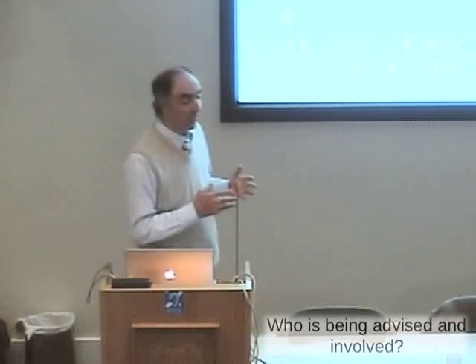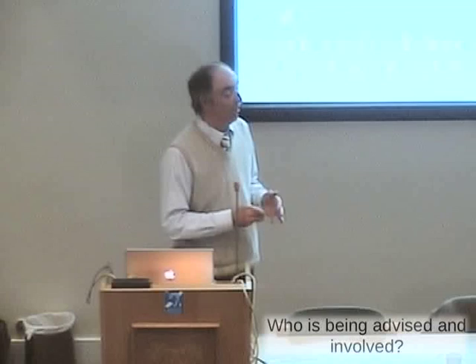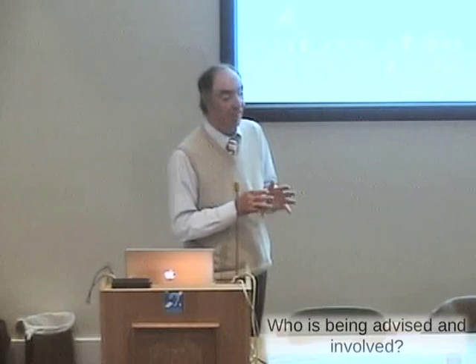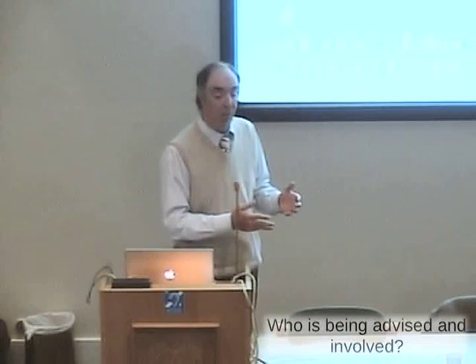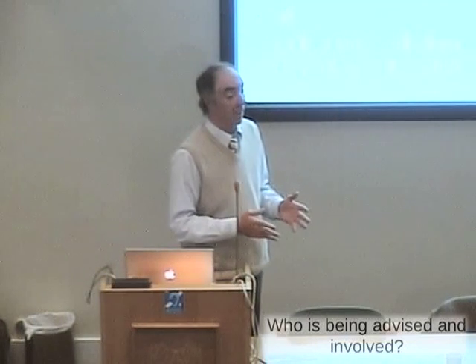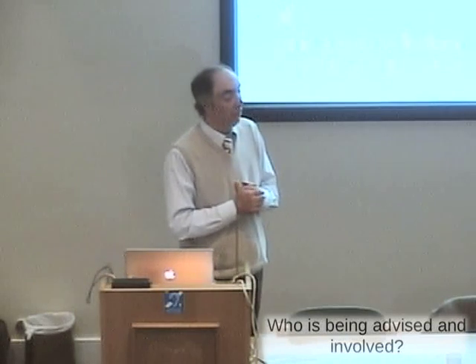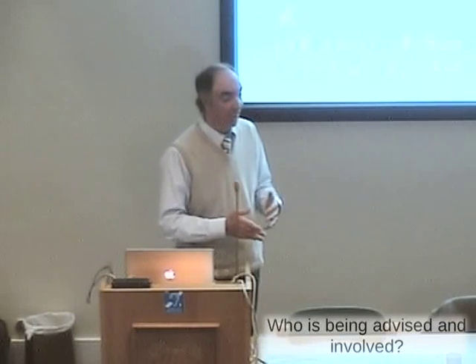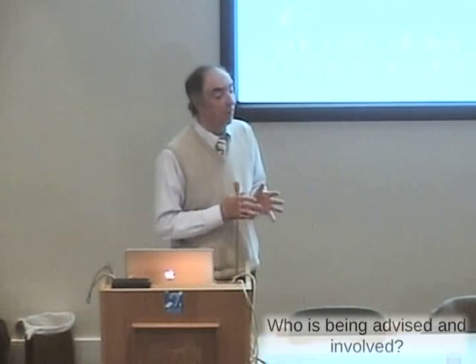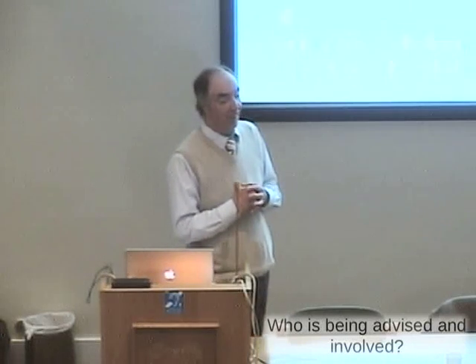LSA programs will be an increasing part of what government asks you to do. LSA stands for Local Self-Audit. And again, it's about institutions being responsible for themselves. So in terms of an X-ray room and the X-ray system present within it, at commissioning, we look at environmental doses. We repeat that at intervals. We are cautious about the maintenance of things like protective doors and screens. We are cautious and we conduct audit on things like the provision of protective clothing, glasses, and so forth. That's where local self-audit is important.